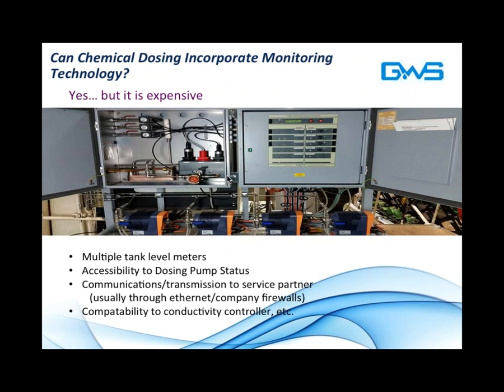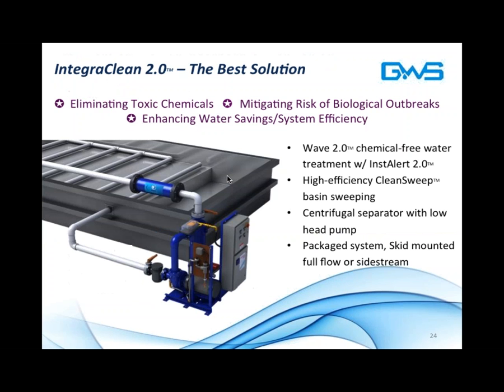Can chemical dosing incorporate monitoring technology? So this has been something that chemical service partners have looked at for many years. And the answer is yes, but it's expensive. Here's a simple example of a system that's used on cruise ships and cooling towers across the country. They require multiple tank level meters, accessibility to dosing pump status, communications and transmission to service partner, and compatibility to a conductivity controller. All of this is to say that costs for such remote monitoring systems are expensive because you're dealing with liquid chemicals and measuring their inputs. Most operators are unwilling to provide or pay for the cost associated with that.